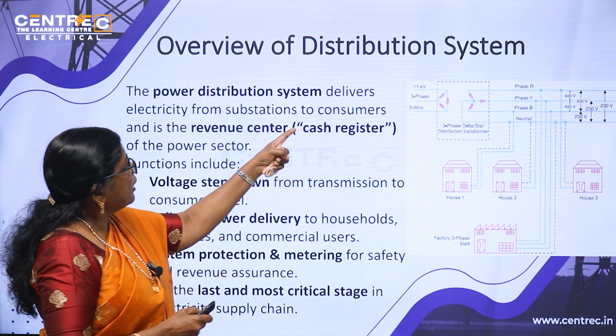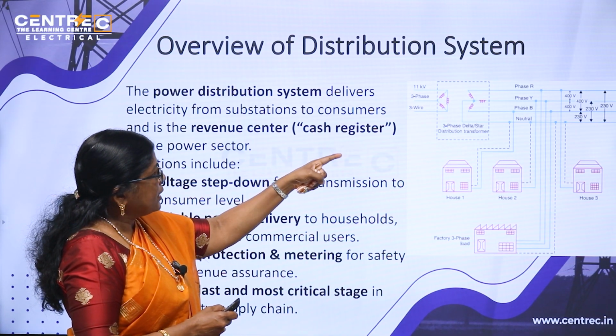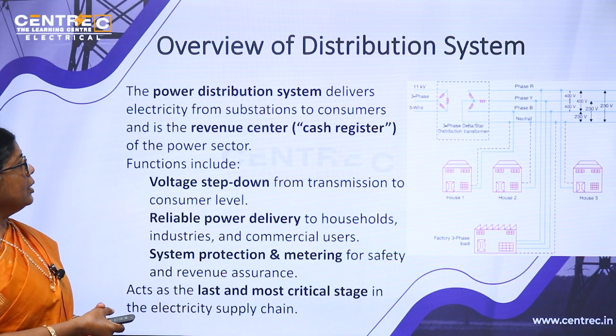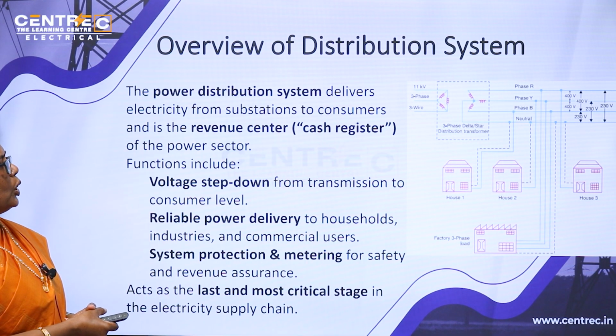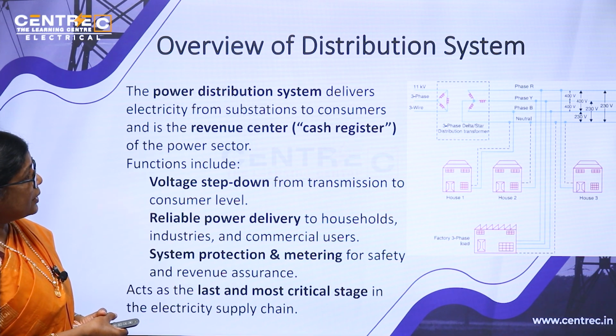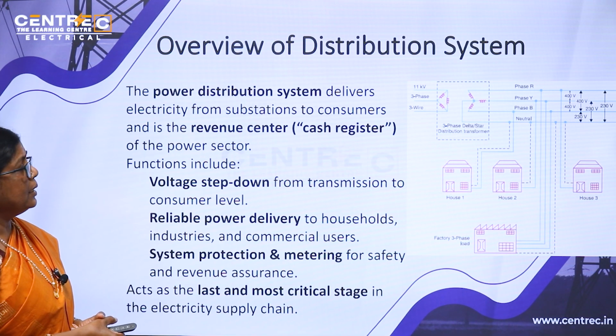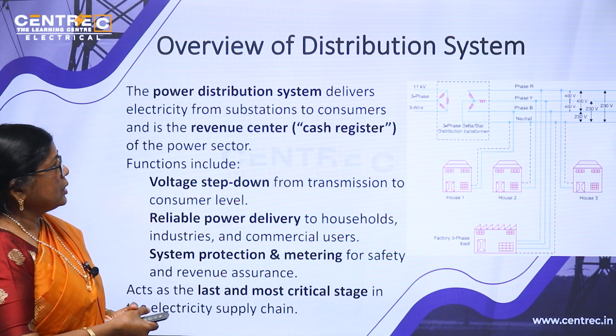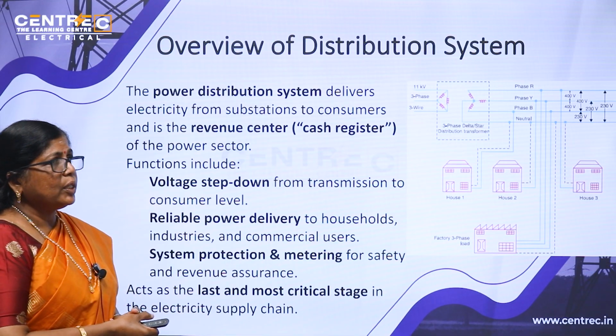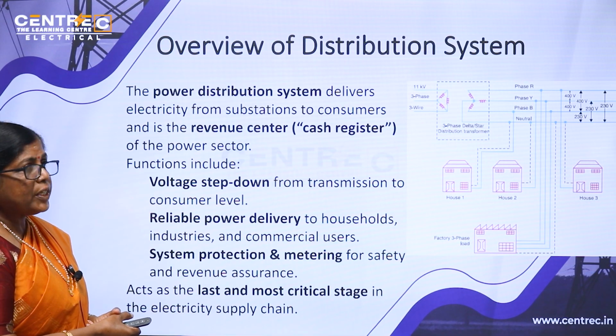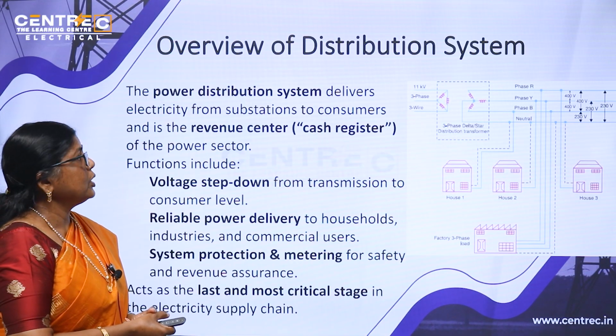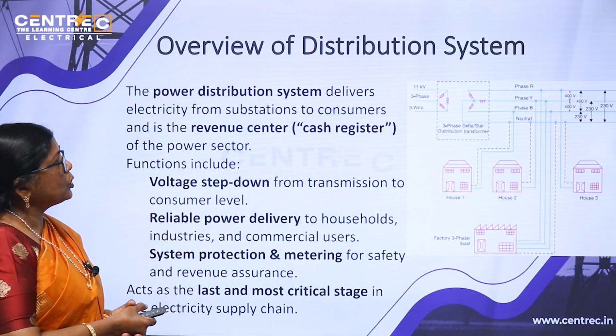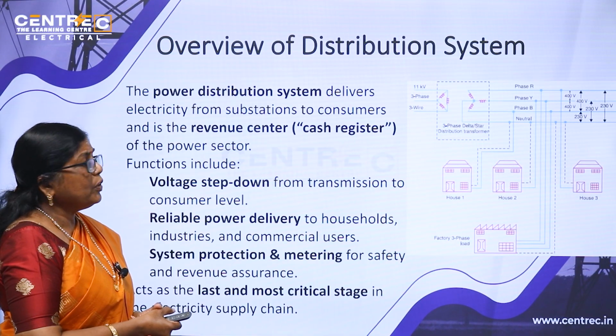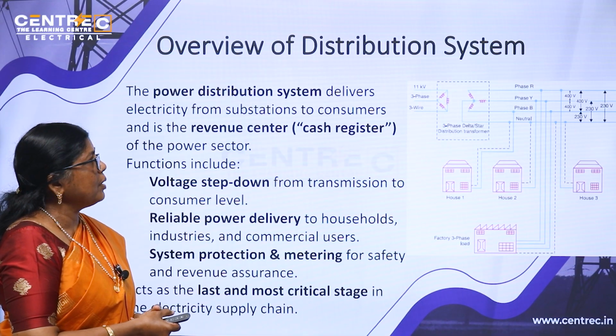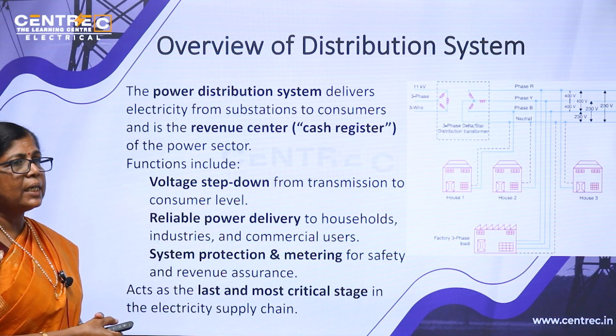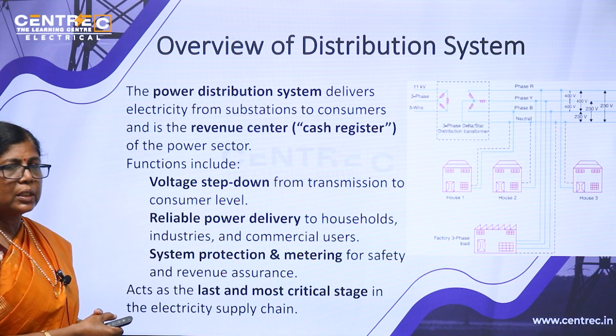our houses. 11 kV, 3-phase delta star distribution. That is an important factor. It is always a delta star, because the input primary side is a delta connection and the secondary is star connected, because we have 3 phases and a neutral. If you want a single phase supply, you take 1 phase and neutral. If you want a 3-phase connection, you can also take it from the star. If it is delta, it is not easy to take single phase supply. That is why delta star connection is recommended for distribution transformers.